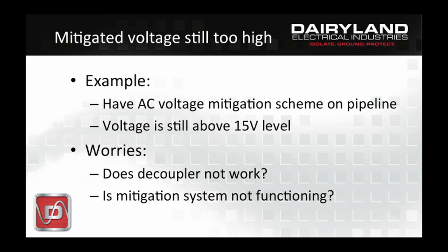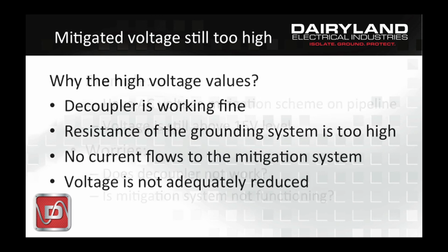The last topic we can talk about is when a pipeline has had a mitigation system applied to it, AC mitigation, for an induction from overhead power lines, and the voltage is still too high. So why would the induced voltage be high if a mitigation system has been employed? They wonder, does the decoupler not work? Or is the mitigation system designed poorly, or is it not functioning?